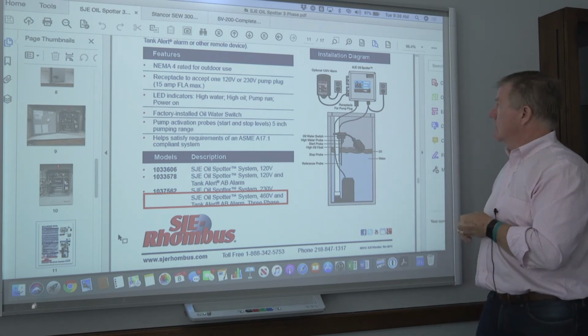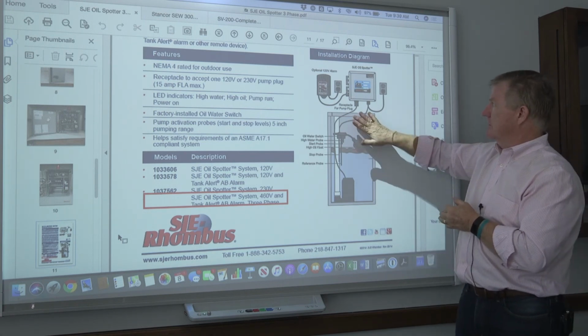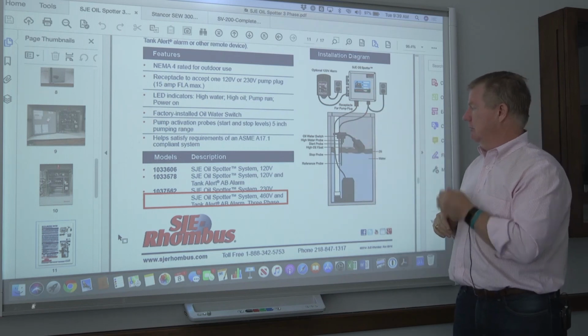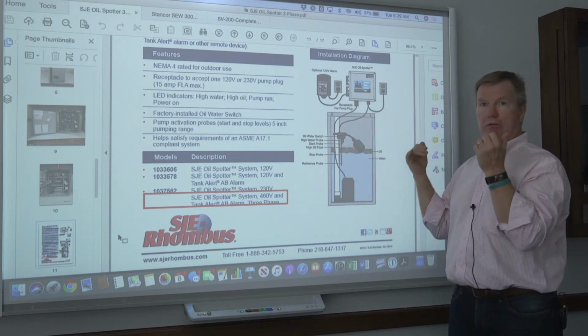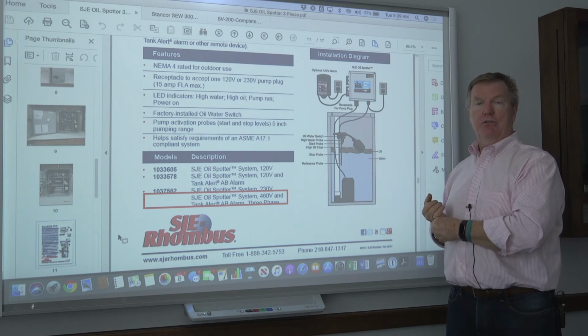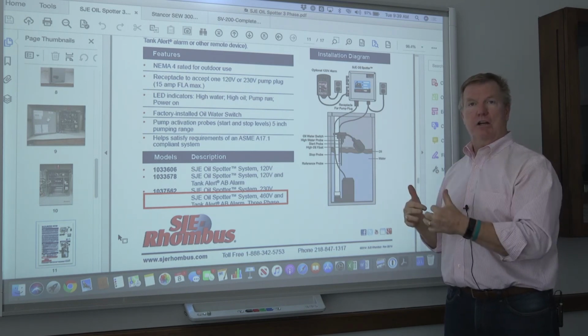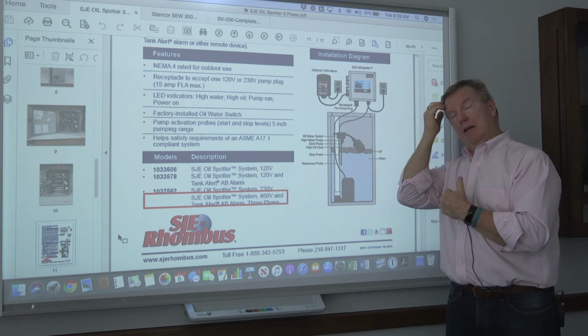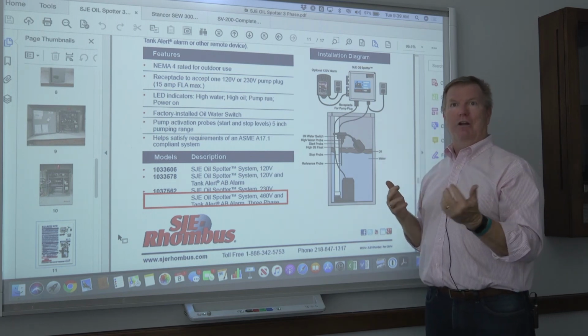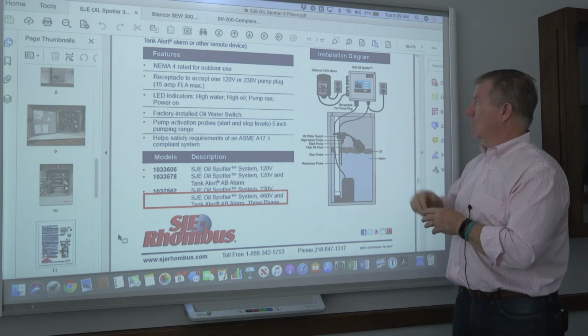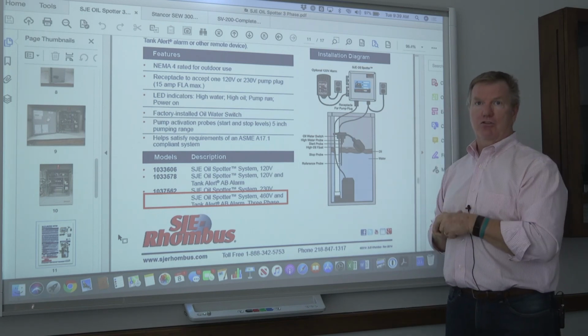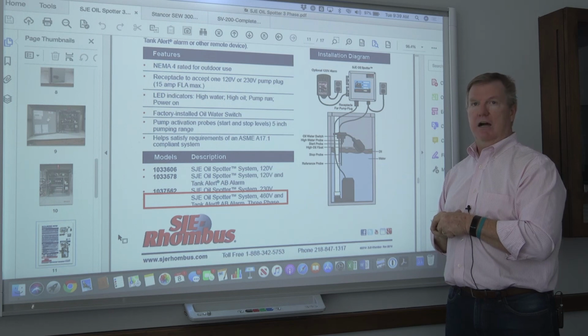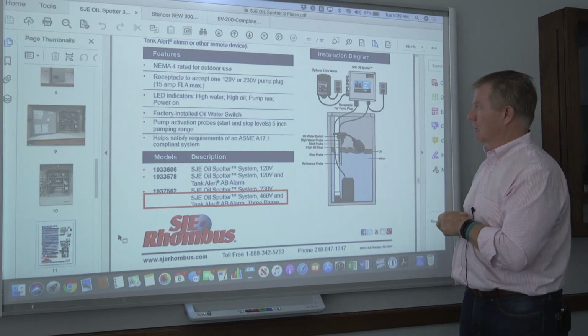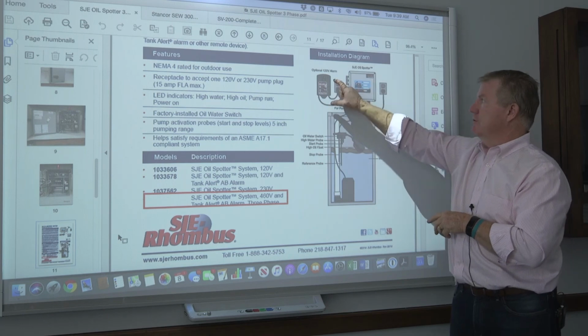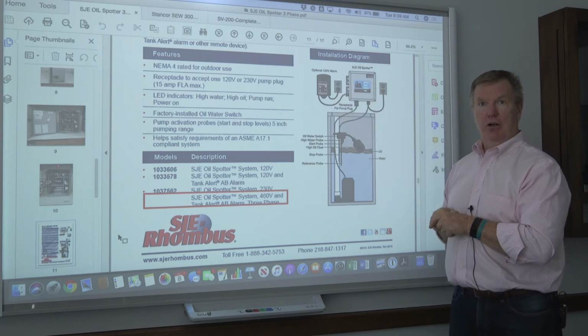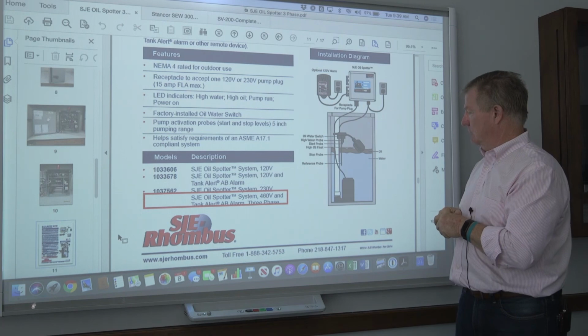Okay, so anytime you're going to work on the electrical part of this unit, of course you want to disconnect the power to it. Make sure that there's not a lot of water coming into the sump while you're working on that, because it'll flood if you're trying to work on it when there's a high influx of water. But always make sure that you remove the power source, disconnect the power, and lock it out before you do any kind of electrical work. And then, of course, any of the alarms, if you have this optional alarm panel, those are going to go also to that level.